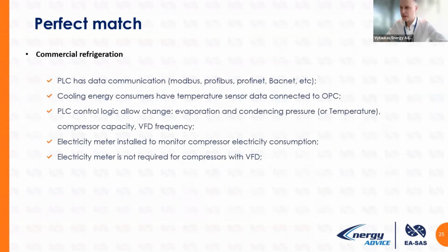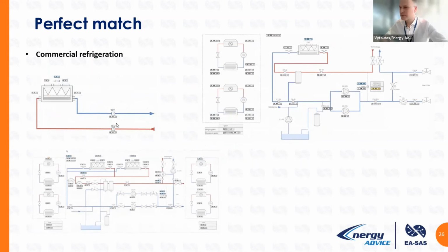If you have a commercial application, usually it would be some PLCs, and we need communication for data transfer, data communications like Modbus, Profibus, Profinet, BACnet, or some kind of protocols. Cooling energy consumers should have temperature sensors, and this temperature should be connected to OPC, PLC, or whatever. Some PLC logic controller should allow us to access and control evaporation, condenser side, compressor capacity, and variable frequency drive frequency. Of course, an electricity meter, you may ask us to prove that our system is working, so you need an electricity meter installed. And if a variable frequency drive is installed, since it has active power metering inside, you don't need to install an extra electricity meter.